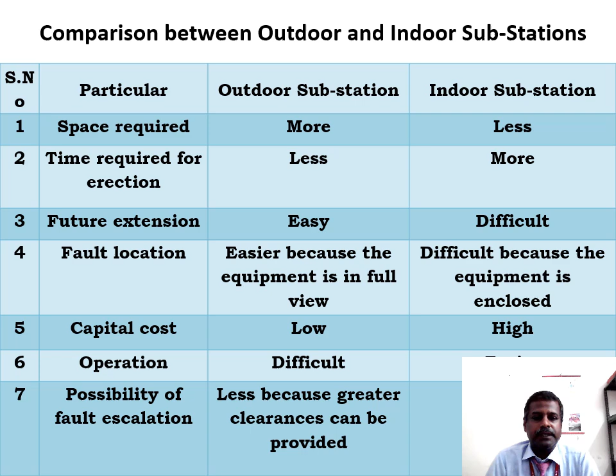Similarly, the capital cost of an outdoor substation is low compared to an indoor substation, which is very high. Operation is difficult in outdoor substations because of frequent maintenance, since it is placed in an open place exposed to rain, storm, external disturbance, and lightning. Operation is easy in indoor substations. The possibility of fault escalation is less in outdoor substations because greater clearance can be provided, whereas it is more in indoor substations.